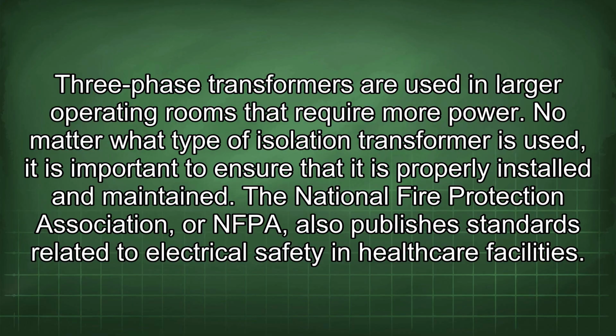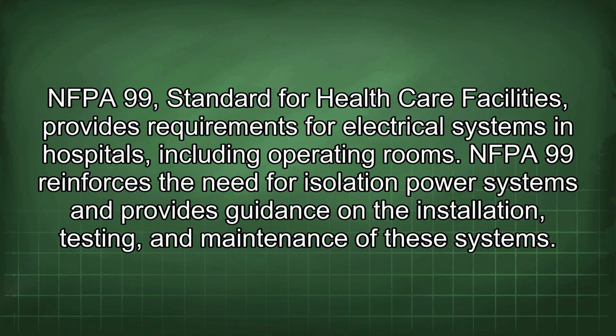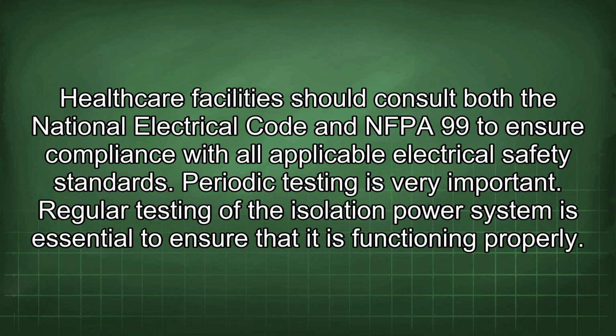maintained. The National Fire Protection Association, or NFPA, also publishes standards related to electrical safety in healthcare facilities. NFPA 99, Standard for Healthcare Facilities, provides requirements for electrical systems in hospitals, including operating rooms. NFPA 99 reinforces the need for isolation power systems and provides guidance on the installation, testing, and maintenance of these systems.